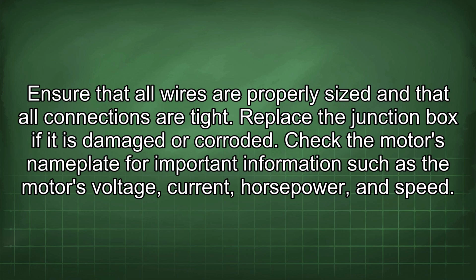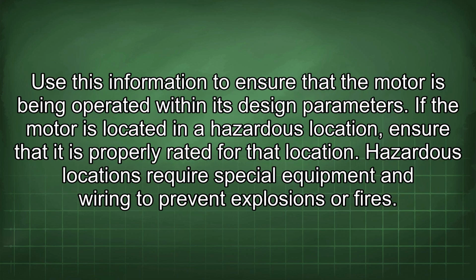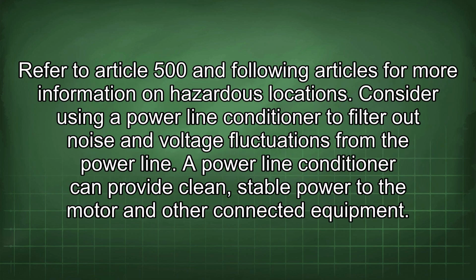Check the motor's nameplate for important information such as the motor's voltage, current, horsepower, and speed. Use this information to ensure that the motor is being operated within its design parameters. If the motor is located in a hazardous location, ensure that it is properly rated for that location. Hazardous locations require special equipment and wiring to prevent explosions or fires. Refer to Article 500 and following articles for more information on hazardous locations.